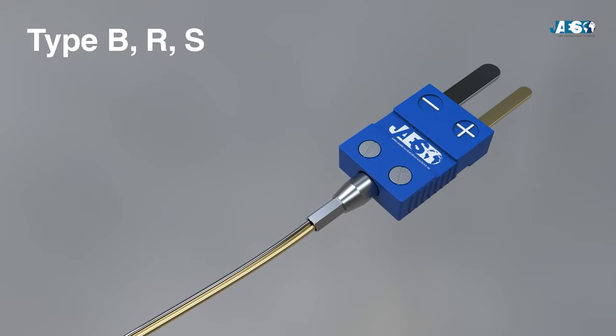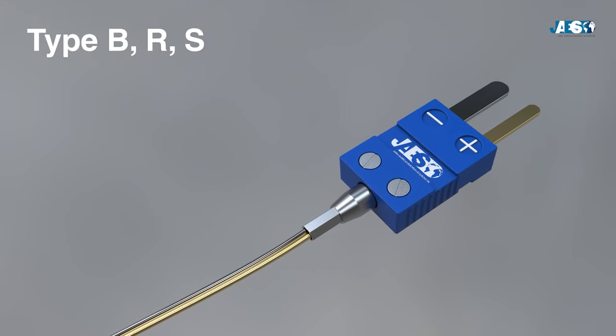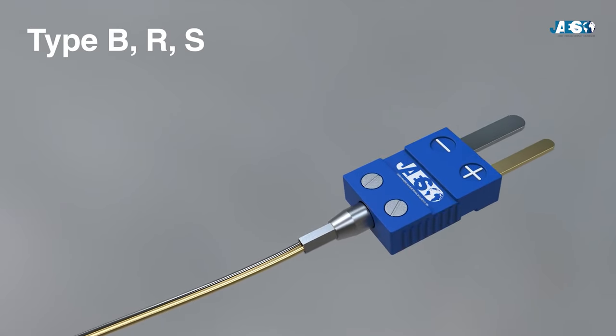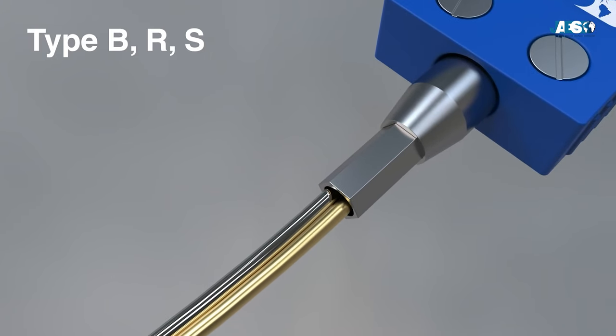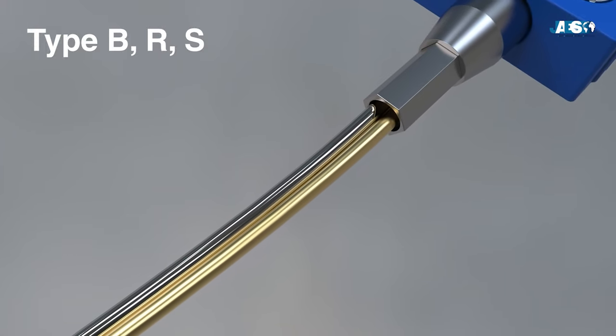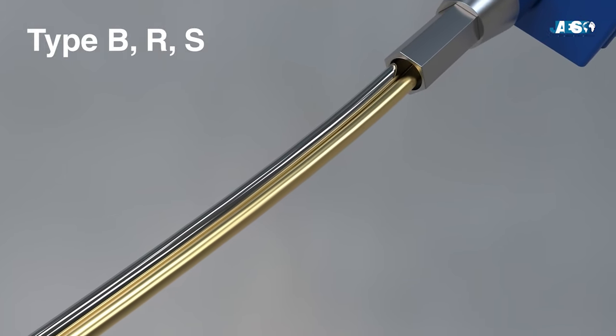Types B, R, and S are those composed of noble metals, or platinum in different percentages. They are the most stable thermocouples, but their low sensitivity limits their use to measurements of high temperatures above 300 degrees Celsius.